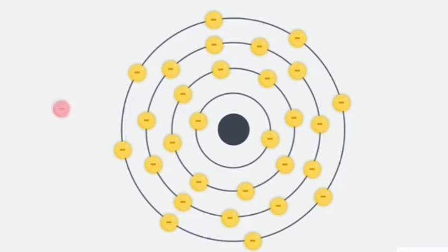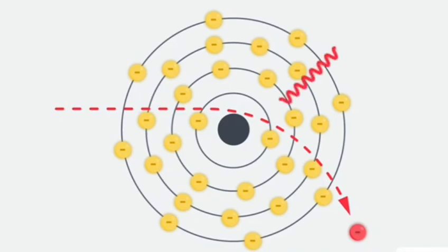When electrons from the cathode enter the anode, some electrons are attracted to the positive charge of the nucleus within these tungsten atoms. And that makes sense. The negatively charged electron is attracted to that positive charge in the nucleus. But when this happens, the electrons slow down or break, and they also change direction, called deflection. This lost energy is released in the form of an X-ray photon.